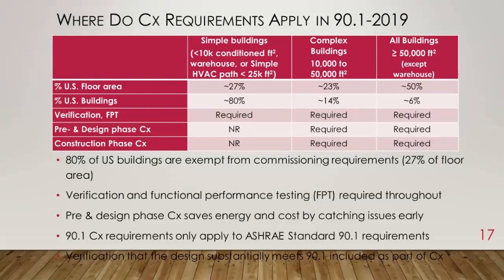And with some of the more conservative parts of the committee, it was important that every little building not necessarily have that added cost of basically a full commissioning process. Then it turns out that the floor area required for commissioning is going to be about 73%. If we add these two columns together, 50,000 is kind of a break point, even though it's 25, because 50,000 was our old level. So for mechanical commissioning, we've added 23% of the floor area.